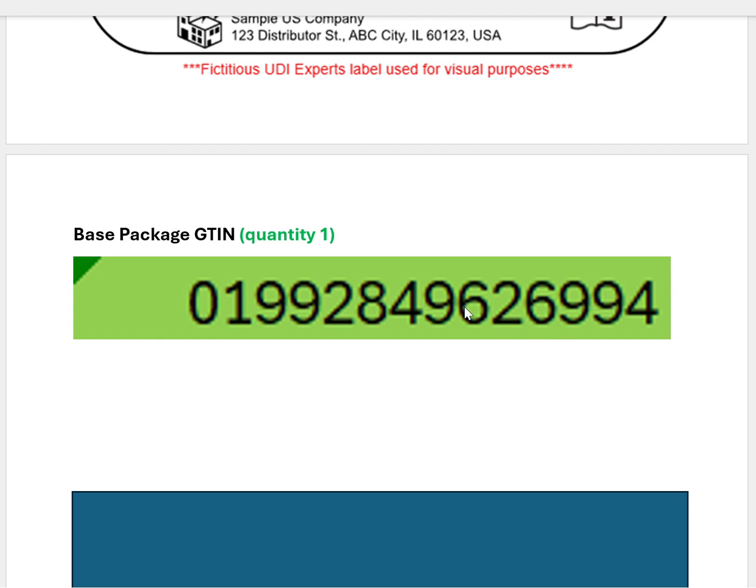After this company prefix number, we have this digit here, 9. This is called the reference item number. This number identifies that specific device for this company, Company A. In this case, 9 is the super tube product. And then the last digit is the checksum digit, and it's calculated. If we put these digits into the GS1 calculator, we'll get this final digit of a 4.